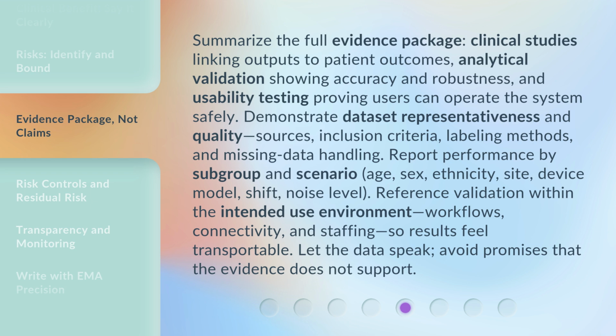Report performance by subgroup and scenario: age, sex, ethnicity, site, device model, shift, noise level. Reference validation within the intended use environment, workflows, connectivity, and staffing, so results feel transportable. Let the data speak. Avoid promises that the evidence does not support.